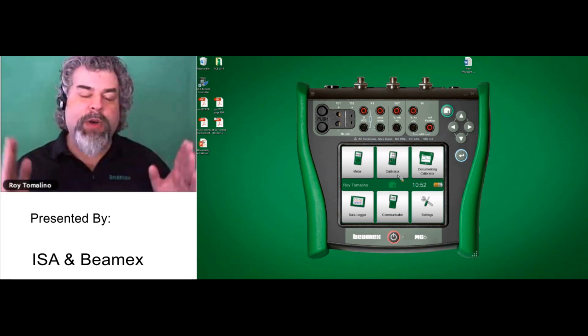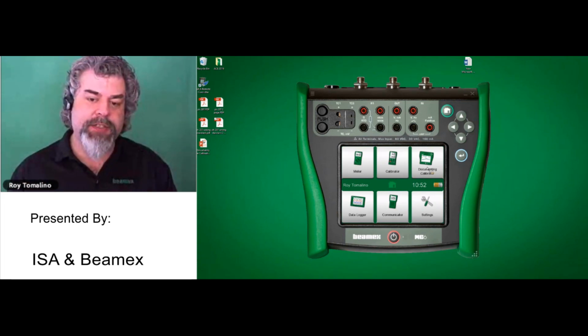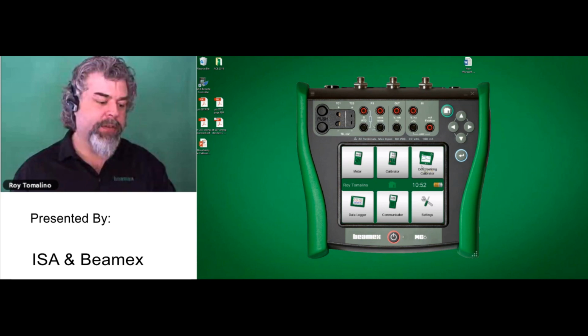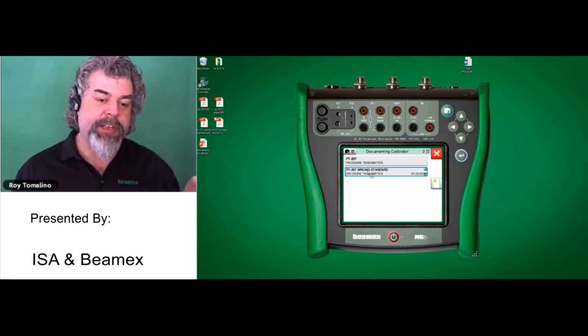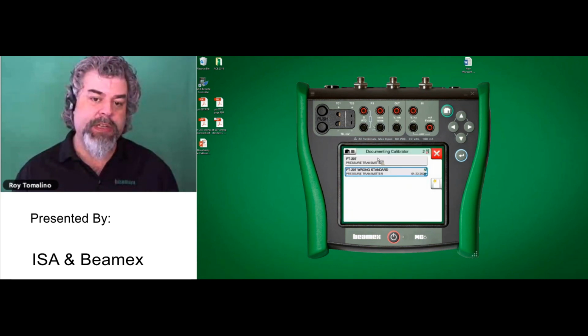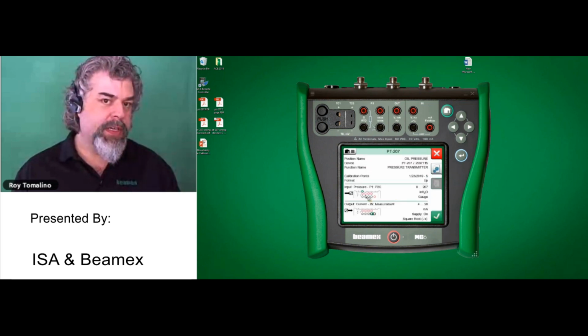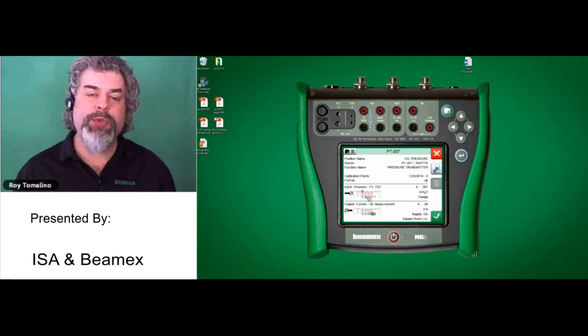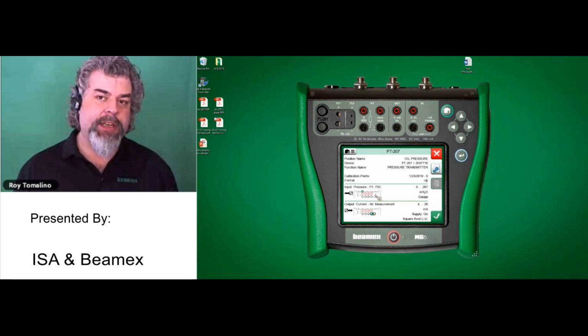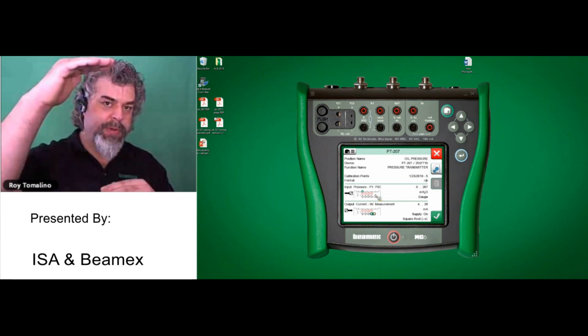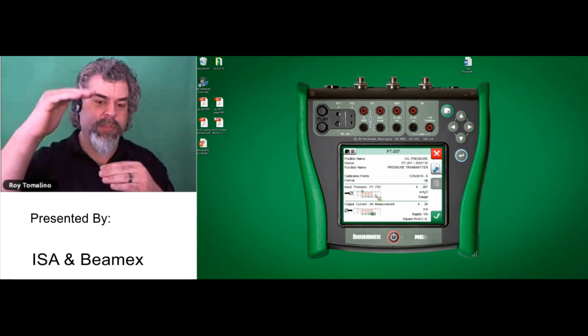So what I have here is another test. Let me go to Documenting Calibrator. We already did PT207 with the wrong standard, and let me go to the correct one. This one is using a 30 PSI module. Again, I'm calibrating 207 inches. My first one was using a 300 PSI, which is just monstrous for this little test.